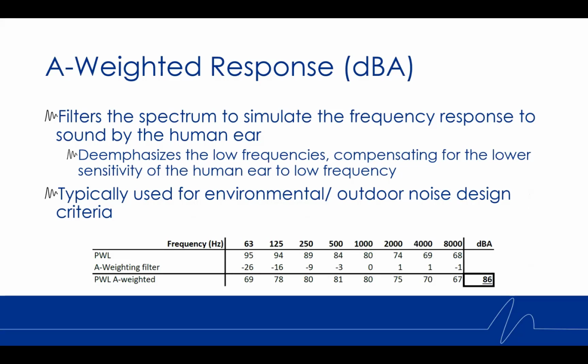Outdoors, we'll use something called an A-weighted response, or dBA. This might be something that you've heard before, a dBA level. And essentially what we do with the dBA level is we look at the raw sound power data for a piece of equipment, or we look at the raw sound power data where the receiver is, or at a property line in an outdoor scenario. We convert this to a dBA number by de-emphasizing the lower frequencies. Just as people, we don't hear low frequencies all that well. We're much better at picking up noises in the mid to higher frequencies. So we really de-emphasize those lower frequencies to give us a better idea of how we're actually going to experience the noise from that piece of equipment.